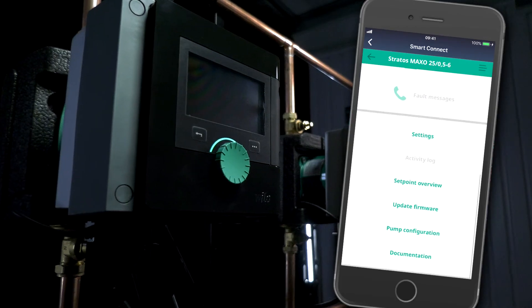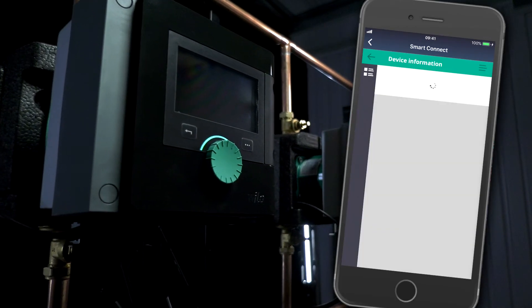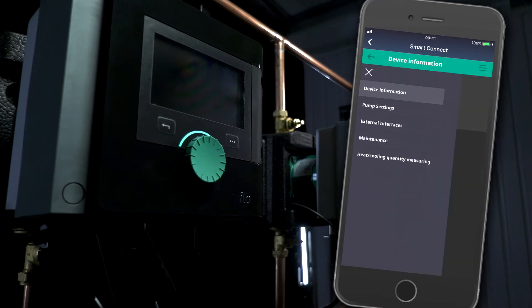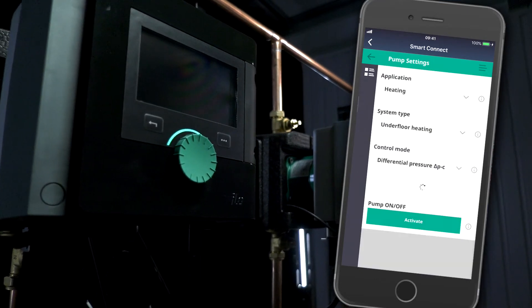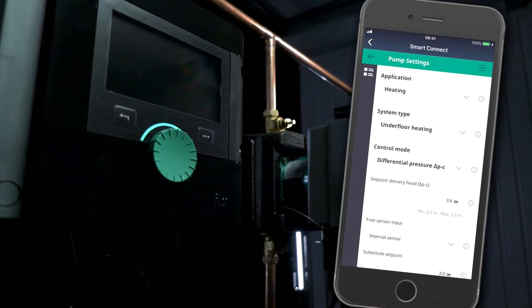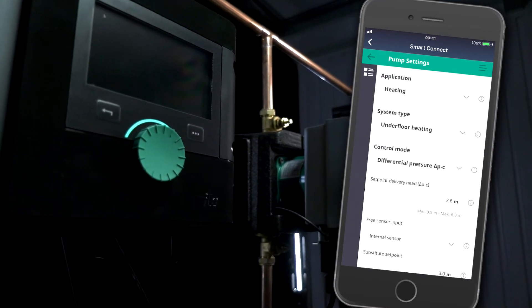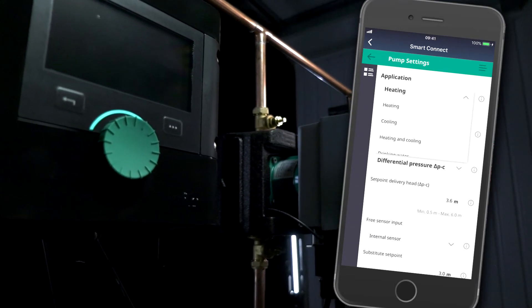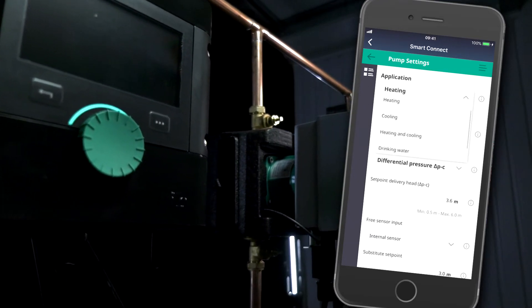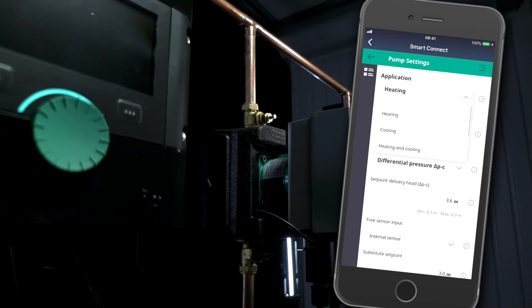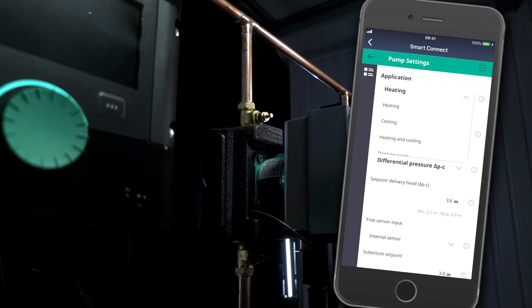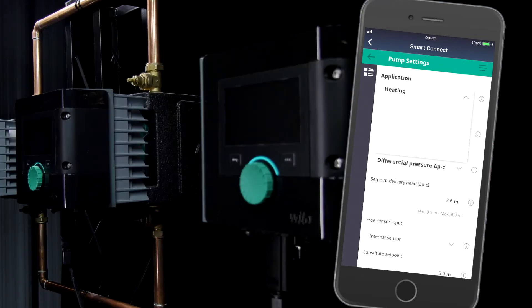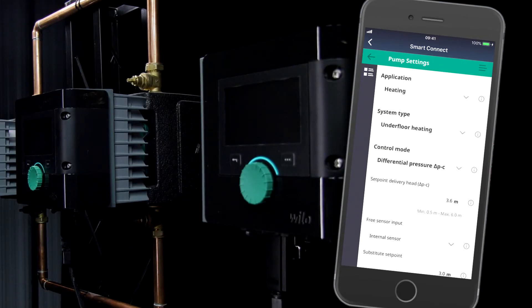If we go into the pump settings section, you're going to see different parameters that you as the installer can change. If we're installing and configuring a new pump or updating the physical installation parameters of an existing pump, so say we add underfloor heating to a system, we can put in the system type, so underfloor heating or radiators.